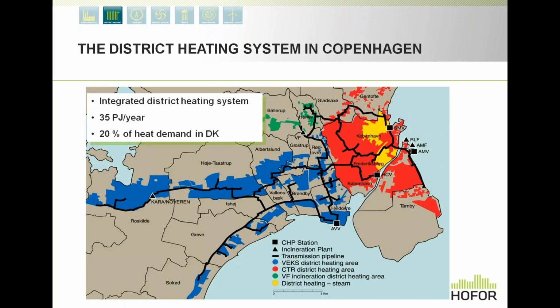The system consists of some very large main CHP stations in combination with incineration plants. These larger plants are all connected to the main transmission pipelines, which run at very high temperatures, high pressures, and high speeds, connected to the distribution networks via area group substations. The distribution networks then run at lower temperatures, around 90-95 degrees maximum on the coldest winter day.